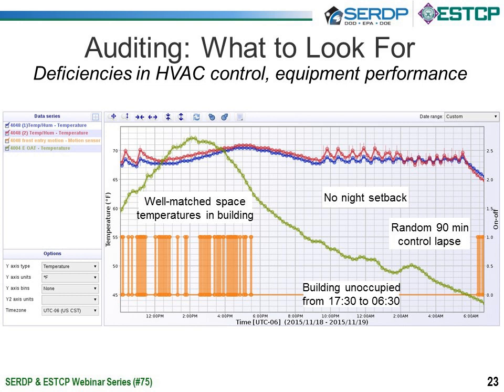So here's an example of results from a gym building on the campus that we did our demonstration on. The maroon and blue curves are plotting the temperature inside the gym. So this is the occupied space temperature. And you can see this sawtooth shape. You can actually see the AC system cycling on and off throughout the day. So one of the key things we're looking at is determining if there's any sort of controlled night setback. So one of the key ways of saving energy with these controls is dialing back the heating or cooling when the building is not occupied.